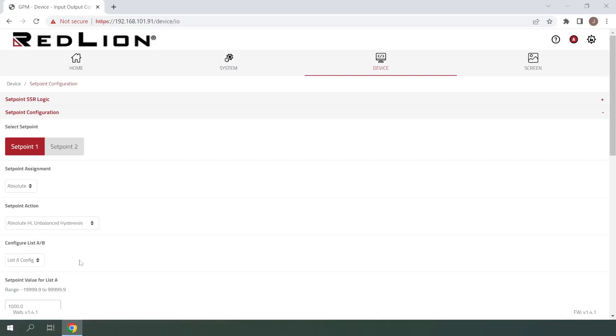The next setting we see here is Configure List A slash B. Each setpoint has a List A value and List B value, with List A being active by default. This feature allows users to quickly change the setpoint value between List A and List B values as needed with a properly configured function key or user input. I'll be leaving this set to List A, as we will not be using List B for this example.